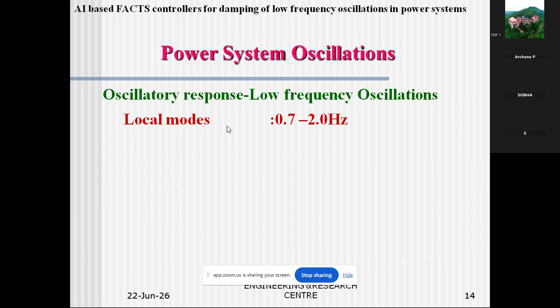You can have two modes of oscillation. One is called a local mode. That is, oscillations are localized in a small part of the power system involving a lesser number of machines. The frequency range is only from 0.7 to 2 hertz. You call it a local mode of oscillations. And there can be inter-area modes of oscillations. That is, the oscillations are felt in a wider part of the power system and involve more machines. The range is 0.1 to 1 hertz. That is, the Kerala grid can oscillate with respect to the Tamil Nadu grid.